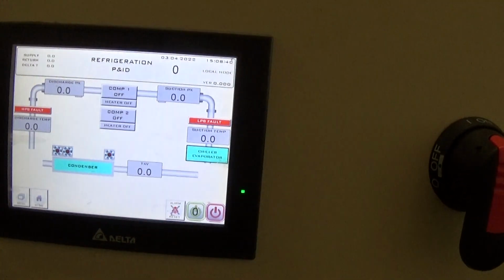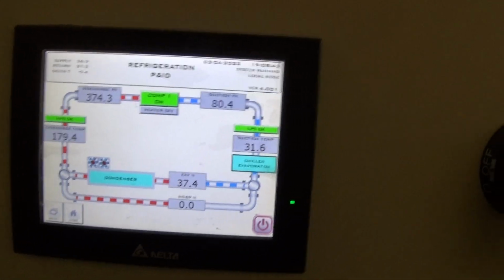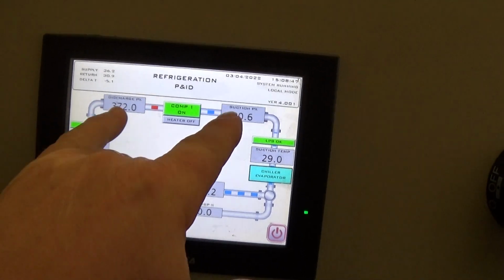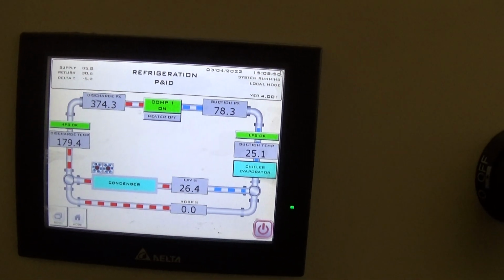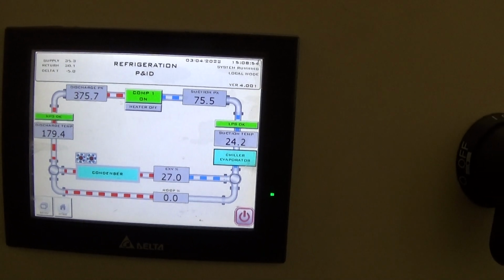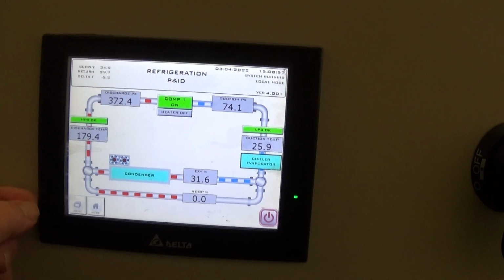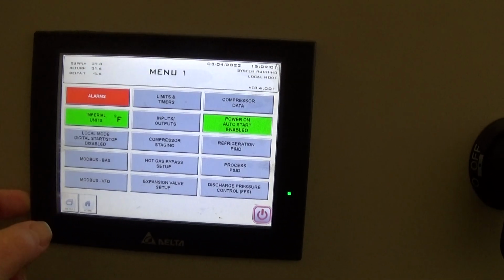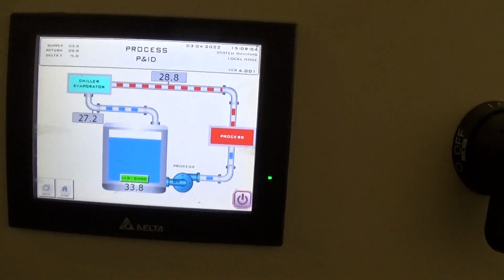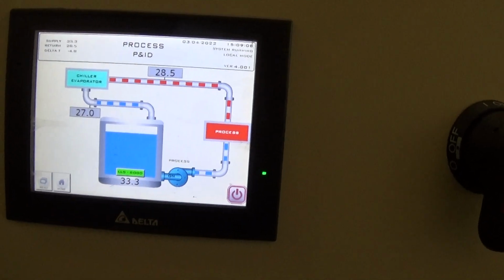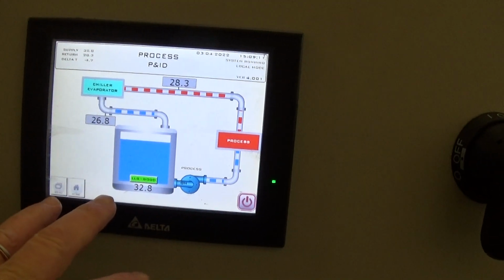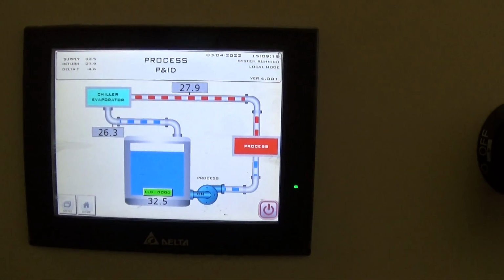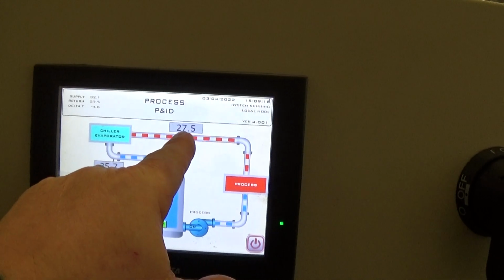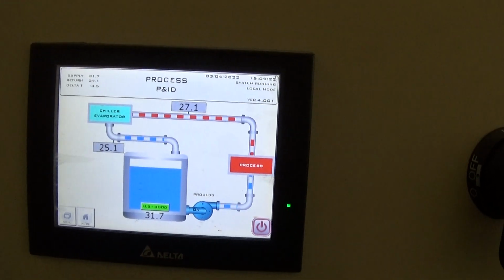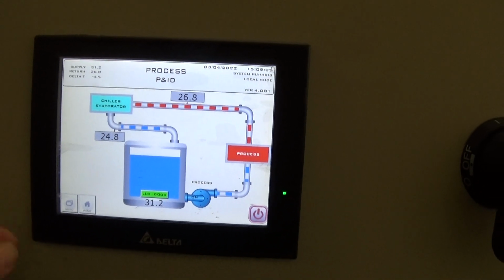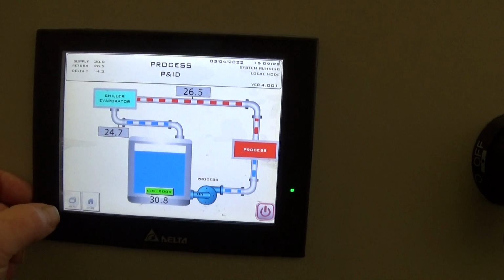This is kind of cool. Refrigeration drawing. Shows you our suction pressure, refrigerant pressure, discharge pressure. That makes sense for this type of refrigerant. But if you ever have a tech come in and he hasn't seen one of these, he'll be completely blown away at all the information that's available here. Process, tank, pump. This is the one thing, I guess, that's really not perfectly accurate now because we modified this as far as just this cartoon or drawing. But we've got these 2 temperature transducers. These are still accurate. You can hear the RPMs lowering now as the load is getting less or as we're getting closer to set point.